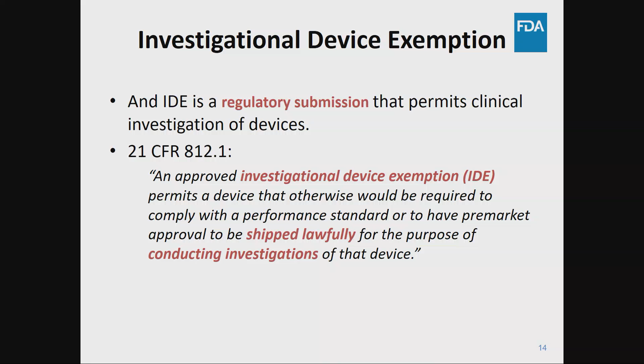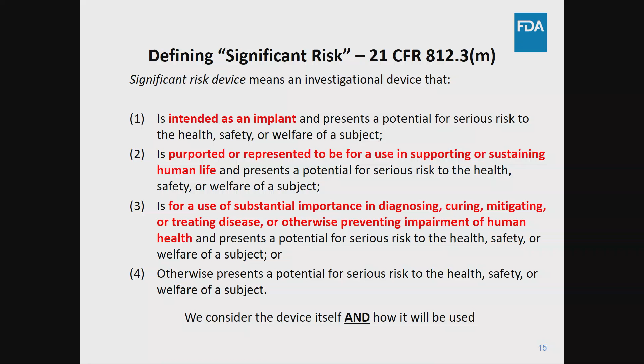One big question is whether it's a significant risk, because if it's significant risk, that requires an IDE. There's significant risk and non-significant risk devices. For NSR devices, they don't require an IDE. They usually work with their IRBs, local IRBs. But for significant risk devices, it hits one of these 4 criteria. It's an implant, typically for 30 days or longer. It's used in supporting or sustaining human life. Substantial importance in those criteria. And the 4th one, which gives us a little bit of flexibility, is otherwise presents a potential for serious risk to health, safety, or welfare of the subject. So if you're using a toothbrush to brush your teeth, probably not a significant risk. If you're using a toothbrush to do brain surgery, we may have some questions. But we consider the device itself, as well as how it would be used, to make a best determination on the risk, whether it's SR, NSR, and whether it requires an IDE.